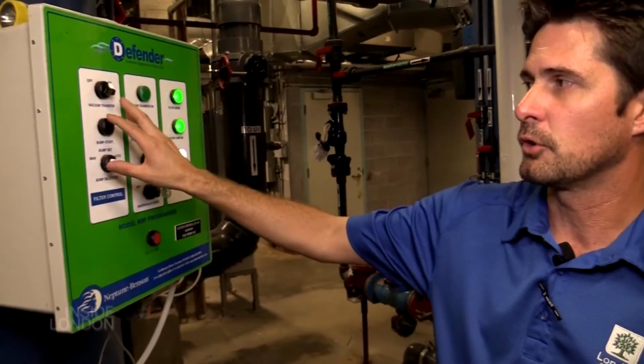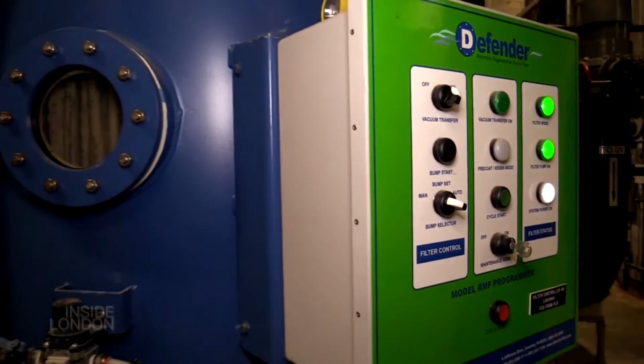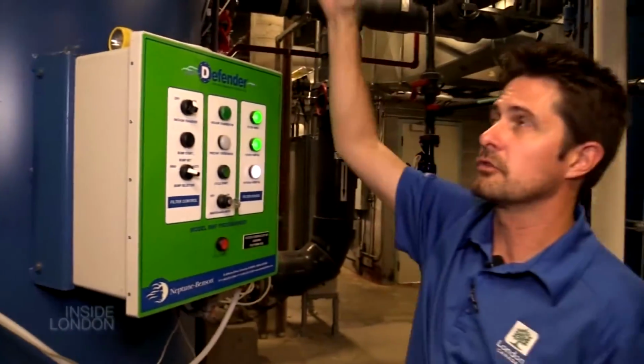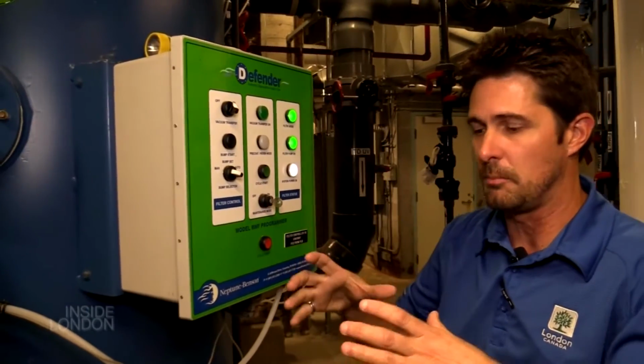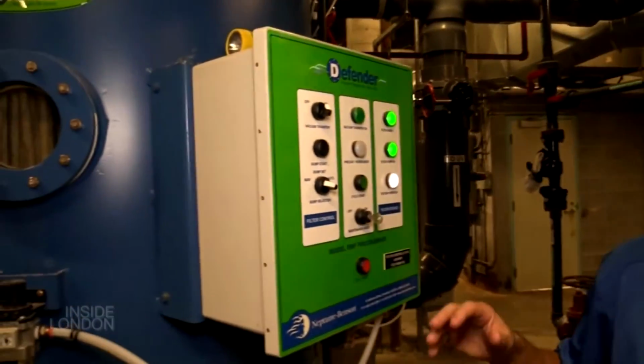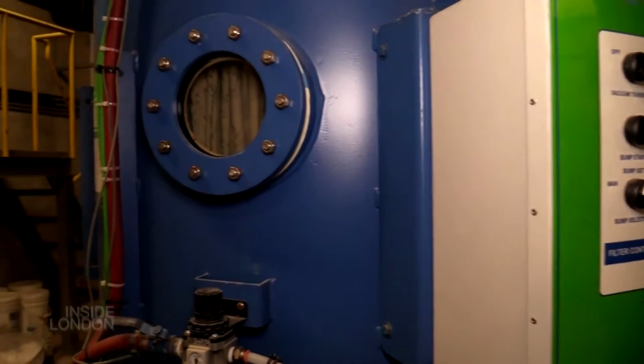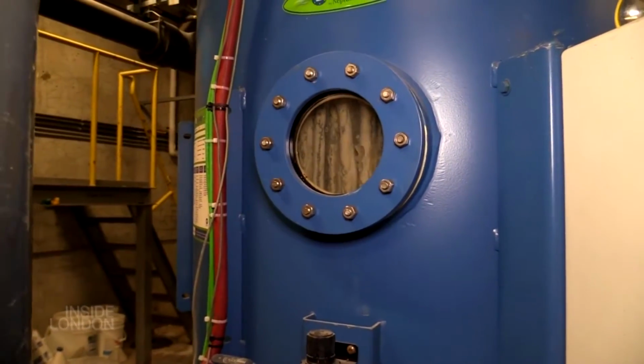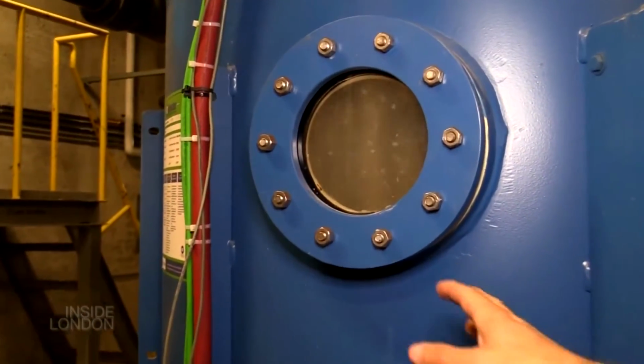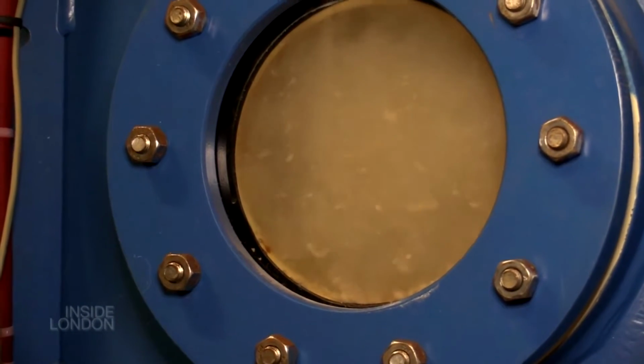What I'm going to do is push this button and we'll put it in what's called a regeneration. And what you'll hear is an air release. There's a plate up there that these tubes are held onto, and air is placed into a bladder on the top of the filter, which depresses it and shakes the tubes, allowing all this filter cake or powder to come off. Then our compressor will recharge the bladder on the top. You'll hear the pump ramp down, get some banging a little bit. You'll see all the powder come off. It goes into a solution.